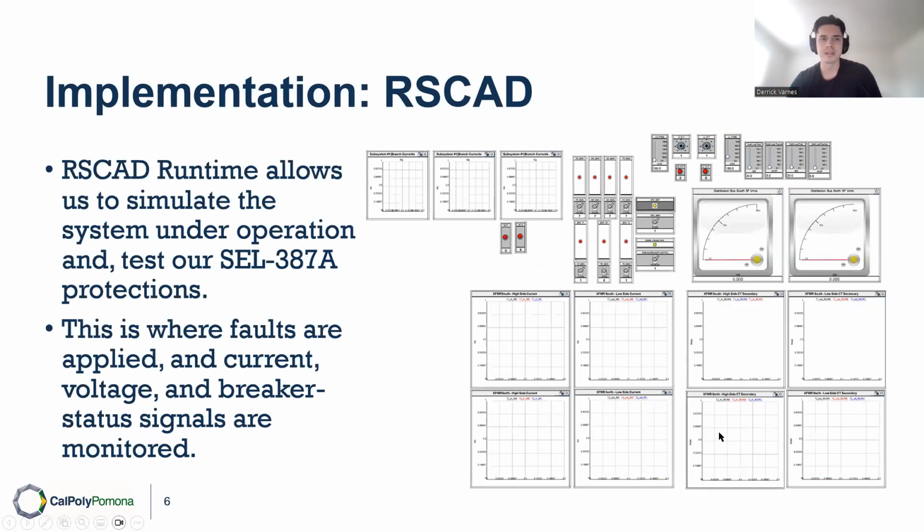RSCAD Runtime allows us to simulate the system under operation and test our SEL 387A protections. This is where faults are applied and current, voltage, and breaker status signals can be monitored. This is a screenshot of our runtime UI.